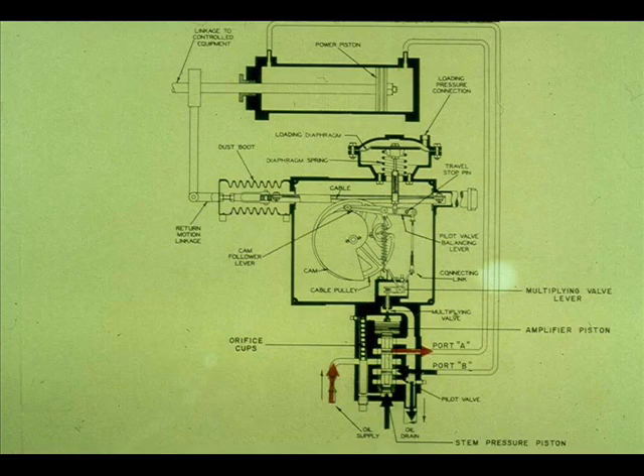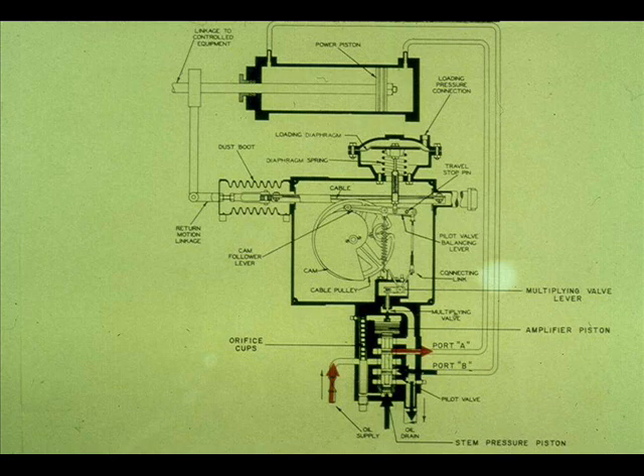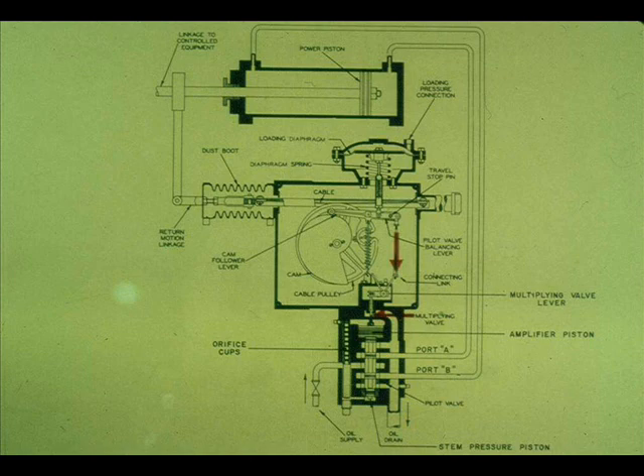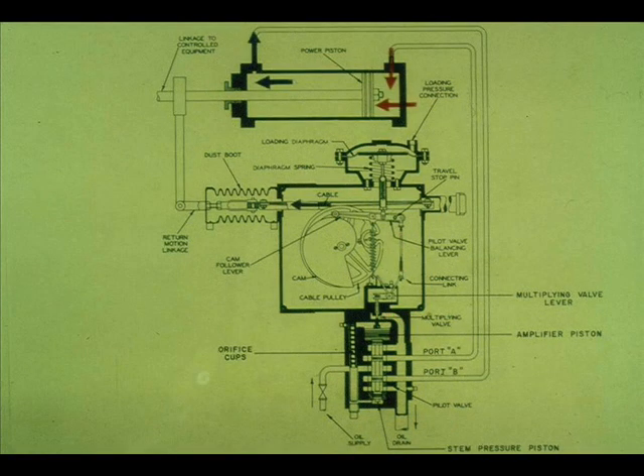Now let's see what happens upon an increase in the instrument signal. The connecting link lowers. This opens the multiplying valve. The amplifier piston is forced up. Port A is connected to supply. Port B is connected to drain. The power piston moves right to left, closing the valve.